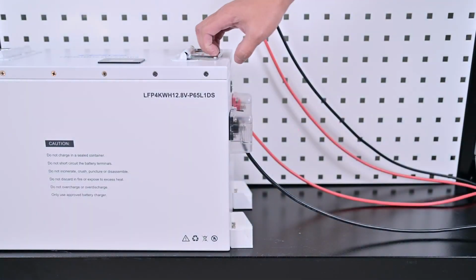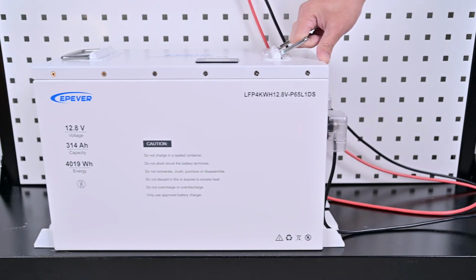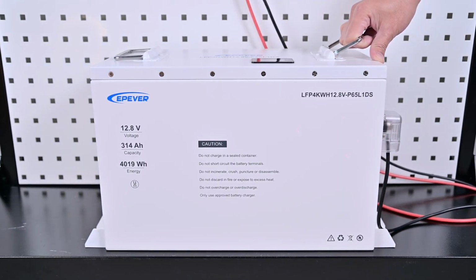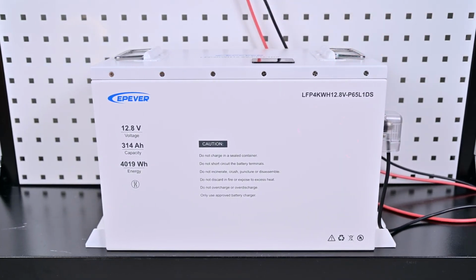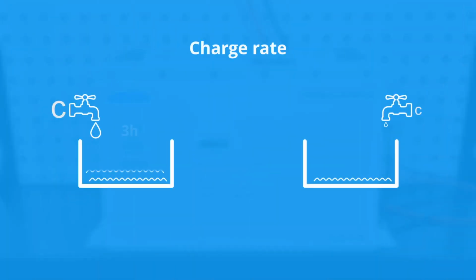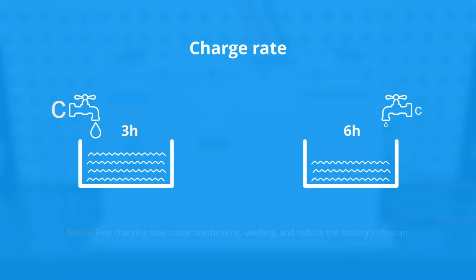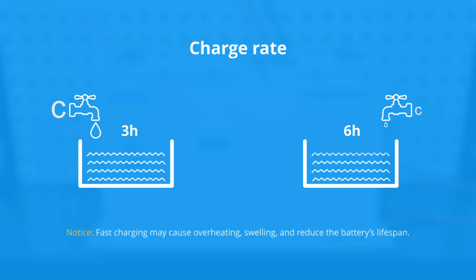Let's talk about the charge rate, which works much like the discharge rate. It describes how quickly energy is stored in the battery, and it's also measured in C. The higher the C value, the faster the battery charges. While it's tempting to charge quickly, especially when power is limited, doing so can cause overheating, swelling, and shorten the battery's lifespan. For the best balance of safety and longevity, we recommend charging at 0.5C.